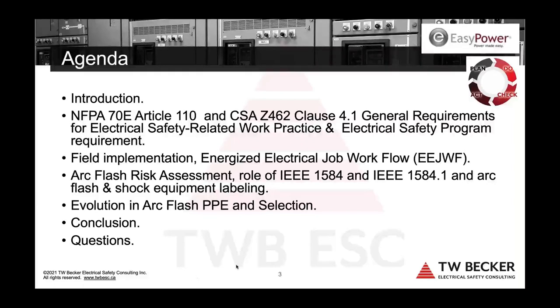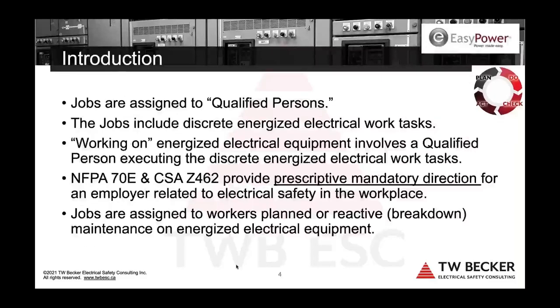So, introduction. The way I framed this from the beginning is it's about the worker, this qualified person. They get jobs assigned to them. They've got to go do that job. They've got to solve the problem in a maintenance role. The discussion related to commissioning systems is still the same. They've got to go commission the motor control center. So ultimately, jobs are assigned to these qualified persons, and then there are discrete energized work tasks. And it's really that discrete energized work task, or multiple tasks to complete the job, where the worker is exposed to arc flash and shock.